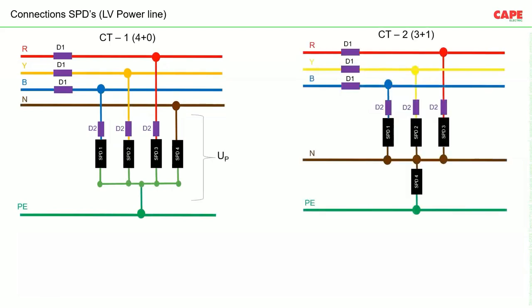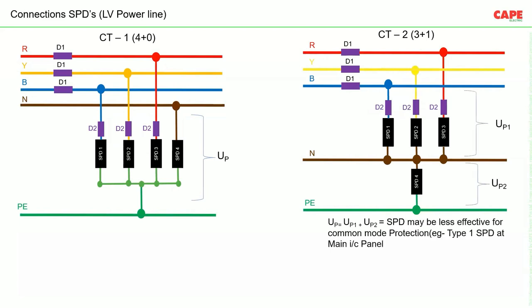In connection type 1 (4+0), the voltage protection level of the complete system equals the voltage protection level of each individual SPD. In connection type 2 (3+1), the effective voltage protection level is the sum of the voltage drop across SPD1, SPD2, or SPD3 plus the voltage drop across SPD4.